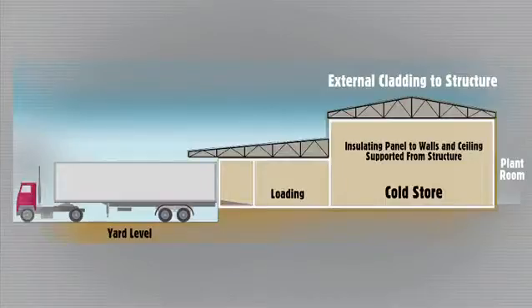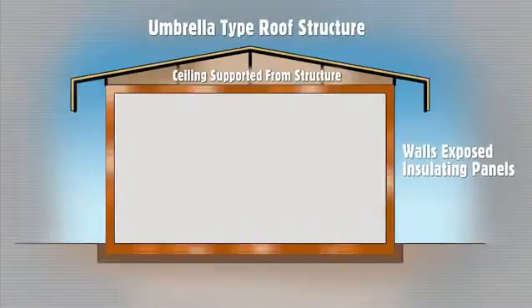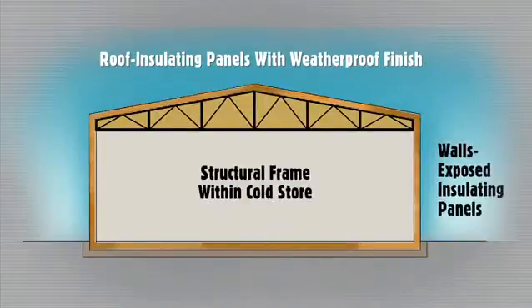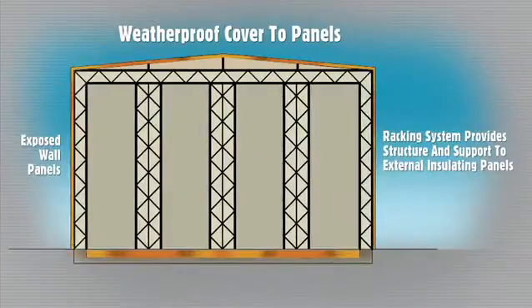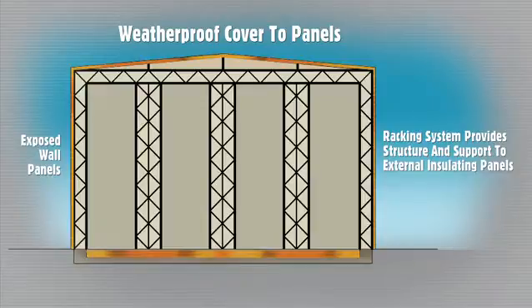For large cold store buildings, there are four different options. The first is an internally insulated store, where an existing building is lined with insulated panels. The second is an externally insulated store, where insulation panels are applied to the outside of the structure. The third is a panel-based store, using pre-fabricated panels assembled on a framework so the store is self-supporting. The fourth is a high-rise store, which is also panel-based but relies on the pallet racking structure to hold up the panels.